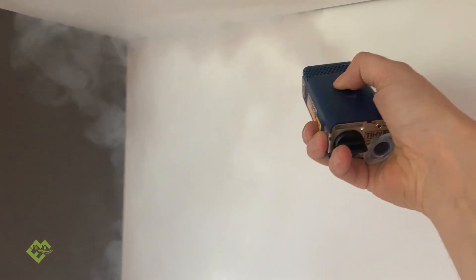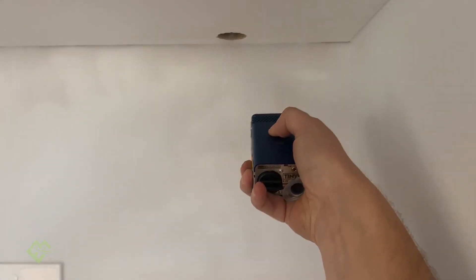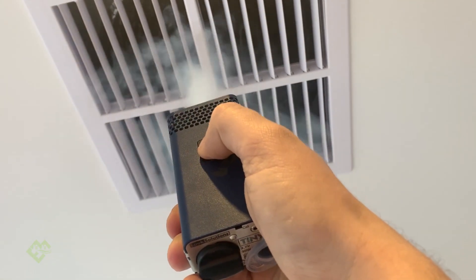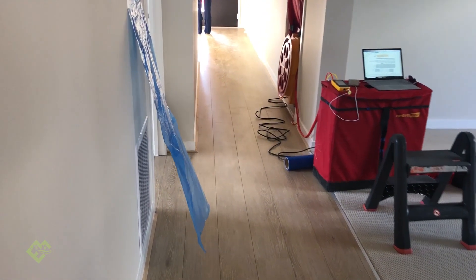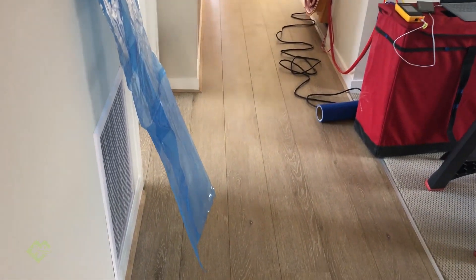However, from our experience going to real buildings and doing the test, a lot of the areas they may miss in sealing are the junctions around your windows, around your doors, the junction between your wall and ceiling, and all the downlight openings — they all add up and may result in not achieving the requirement. Potentially a place where they will definitely come undone is evaporative cooling and ducted heating return connectivity to the ductwork. These are big ticket items that could potentially set these homes over 10 m³ per hour per square meter at 50 Pascal.